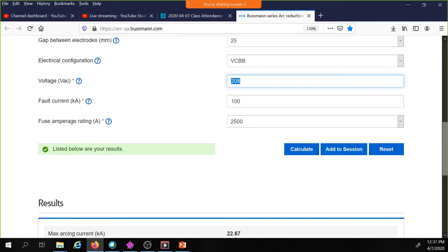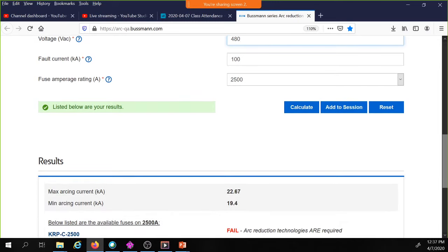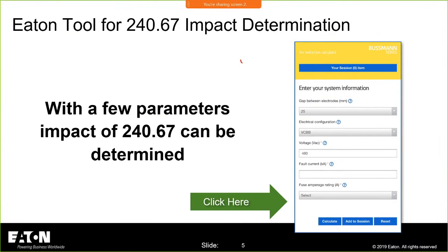If I increase that to 480, and I did a recalculate, remember 19.4, calculate 41. Look at that. I take my voltage from 208 to 480, and I moved my minimum arcing current from 19,000 to 41,000 amps. That will get you a faster clearing time and into the current limiting region of these fuses much faster. So higher currents will get you faster clearing times. So you learned a couple lessons there. This is a good tool. Use it, play with it. If you don't really understand what you're looking at, it's not a tool you're going to be able to use. But you should understand what you're looking at. Don't blindly use tools. Anyway, that's a new tool you can play with. All right, back to our regularly scheduled program.